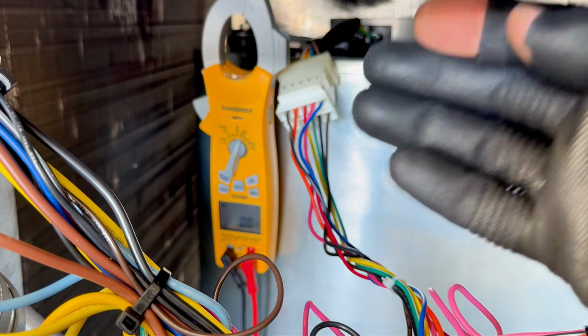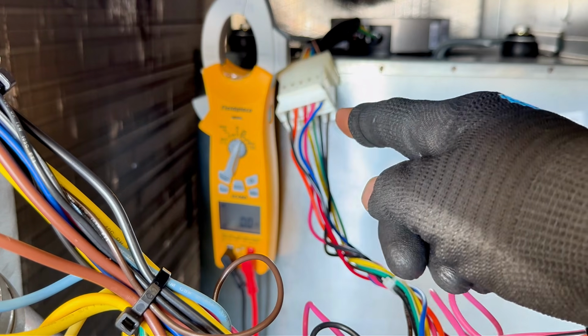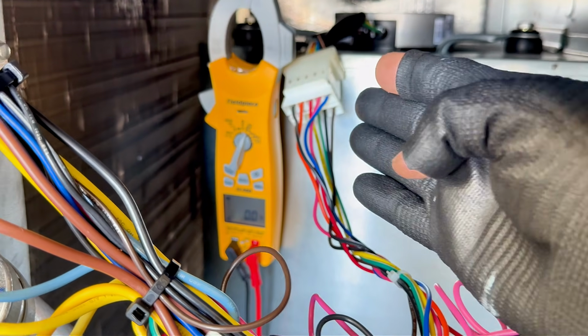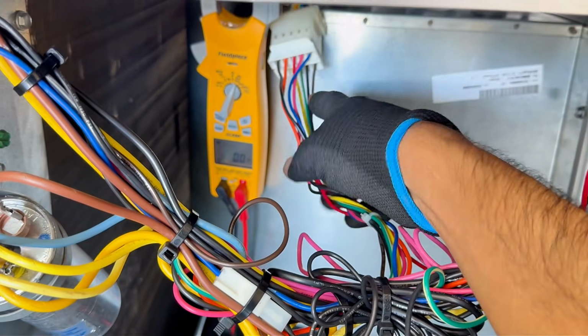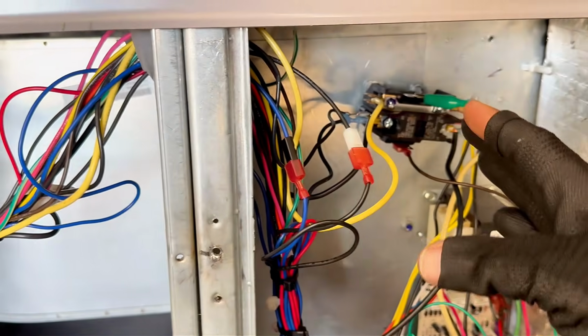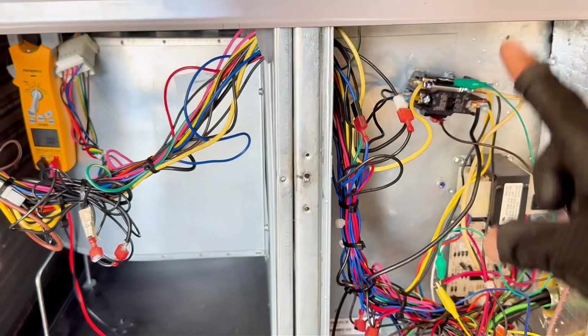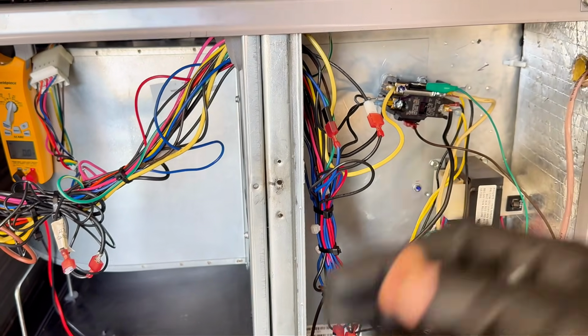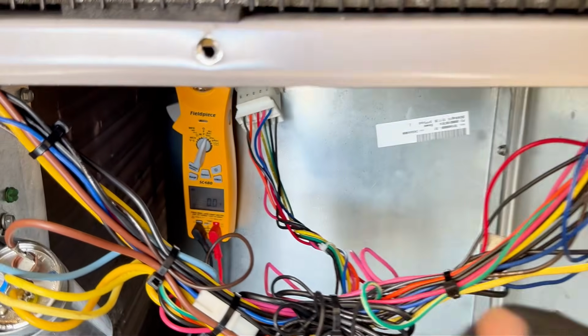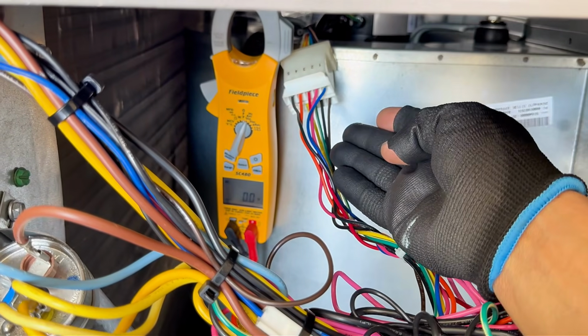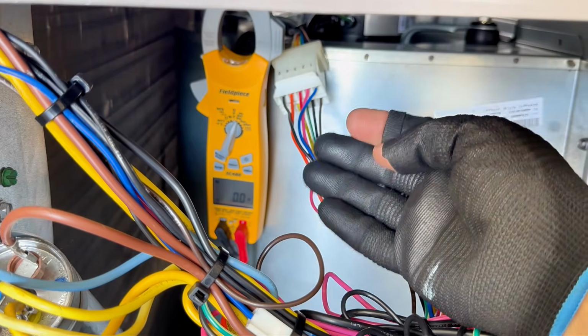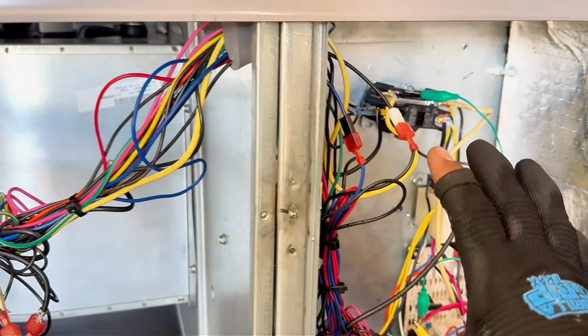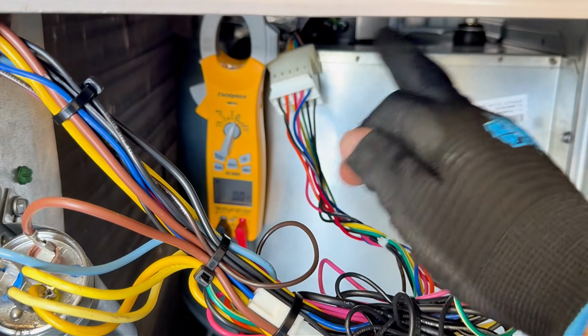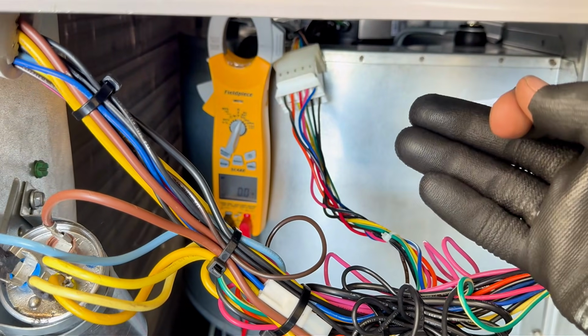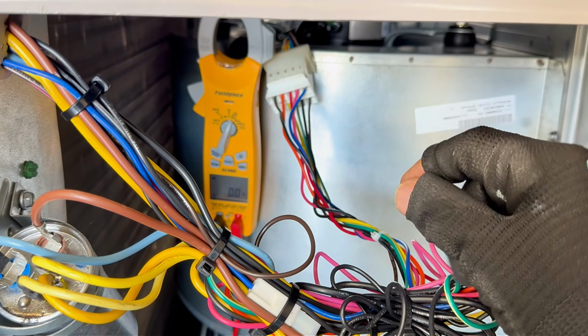But all you're doing is just confirming, and you need to confirm that you have low voltage and high voltage present. Now, of course, confirm that all the wires from here go all the way back and that everything's wired correctly, that any wires are not cut or ripped. Make sure of that first. And when you call for cooling, you're gonna confirm high voltage and low voltage. If you don't have it, then you have to go back over here. What's going on? Why aren't we sending power over here? If we do have it and the motor is not spinning, then most likely the module on the ECM went bad.